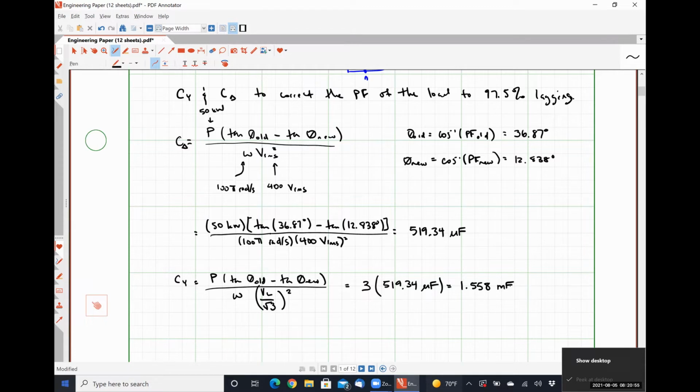Well, it's a delta-Y conversion on a capacitor bank, right? Which is just an impedance. And we know for a balanced Y-connected impedance and a balanced delta-connected impedance, to convert between those two, it's multiplying or dividing by a factor of 3, right? It actually goes in the opposite direction that we would think, because capacitor impedance is inversely related to the frequency, right?